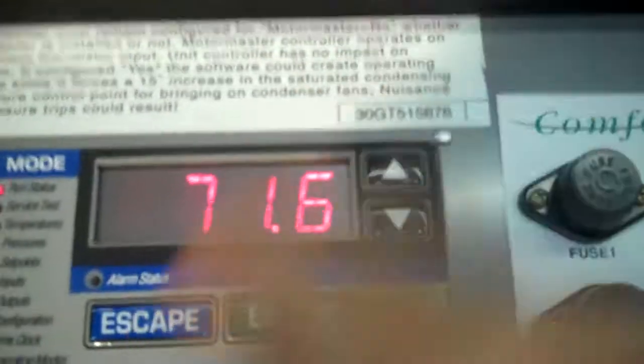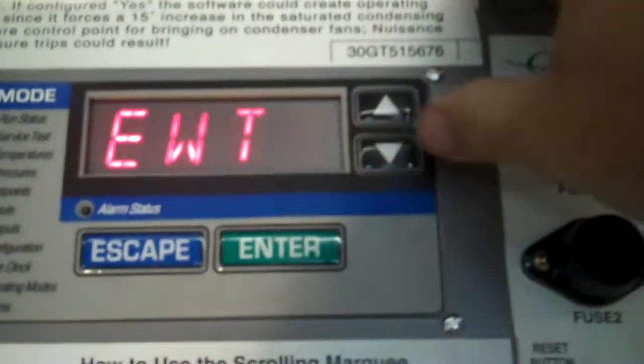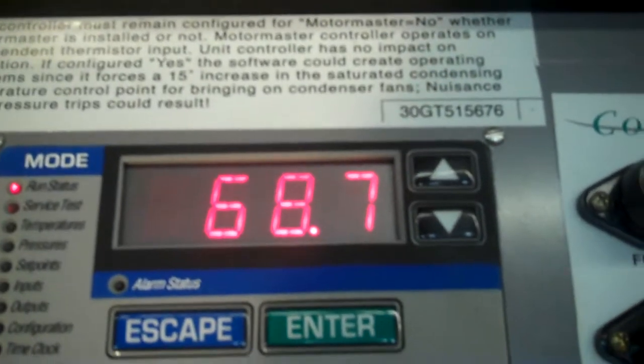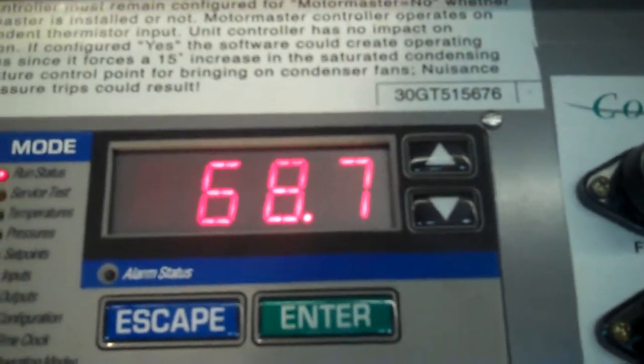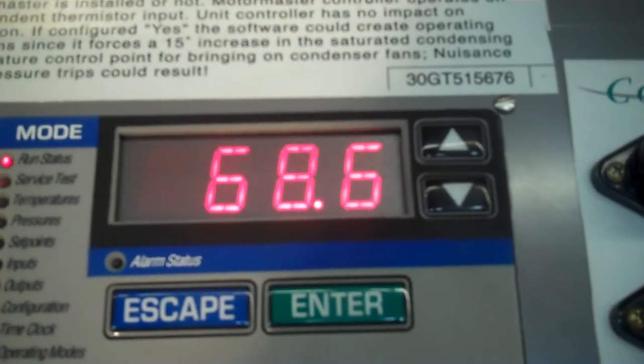You can see just our connections back there to the chiller barrel. You can already see it's starting to chill a little bit. That's the entering water temperature. But let's go to the leaving water temperature, which will obviously be a little bit colder — 68.7 degrees.